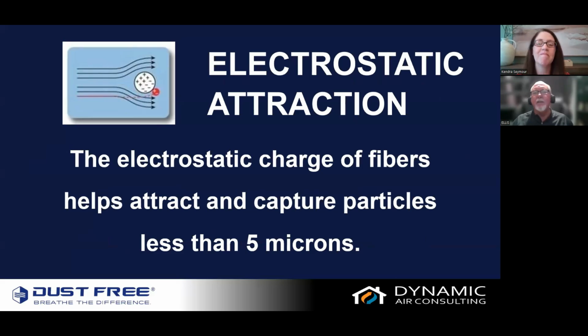Electrostatic attraction has to do with what the filter media is made of. When we look at synthetic materials like polypropylene, the best illustration is if you take a balloon and rub it on your arm and it sticks to the wall—that's electrostatic attraction. As air goes across these synthetic materials, they naturally get an electrostatic attraction, just like rubbing a balloon on your arm, and then the particles stick to them as they go by.